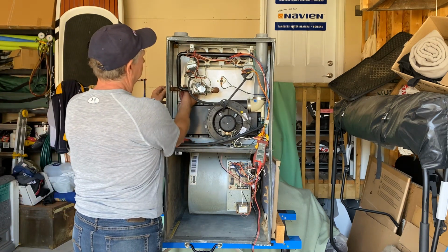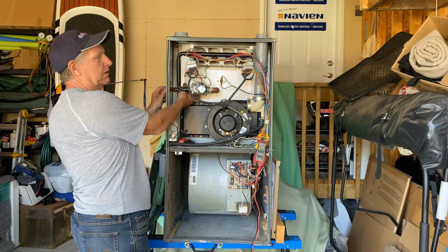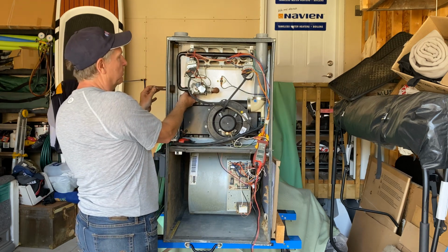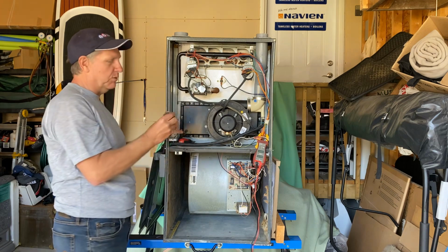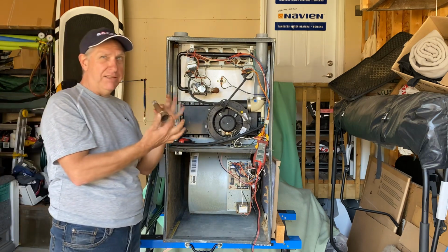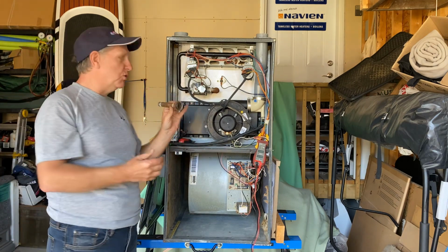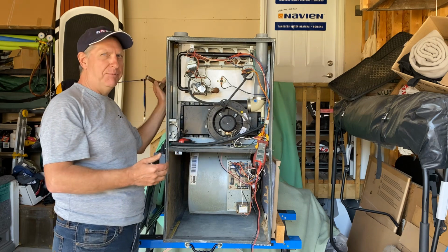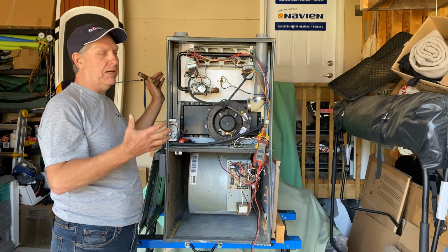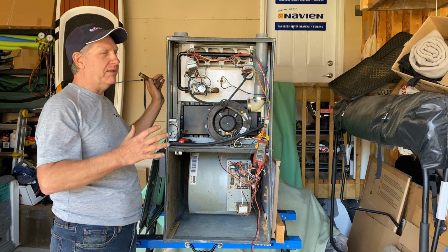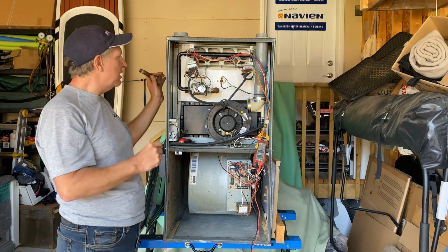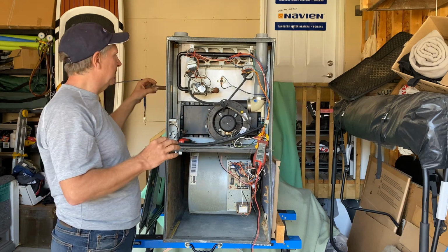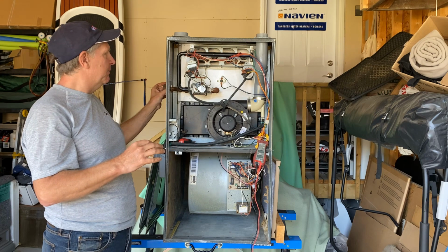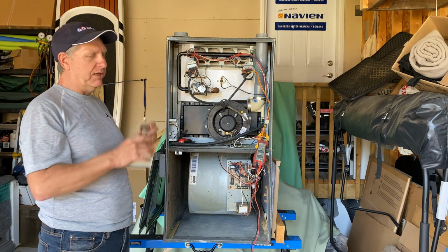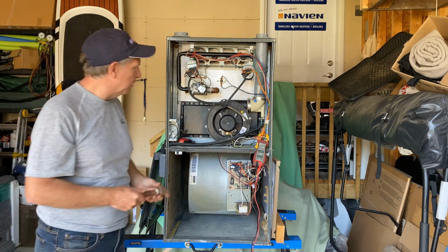Obviously you would need wrenches to do this in the real world. It's got a union here. Technically, I think the union should be outside the cabinet - my recollection isn't 100%, but I'm pretty sure code says the union has to be outside the cabinet. Don't quote me on that, you have to look at your code book.